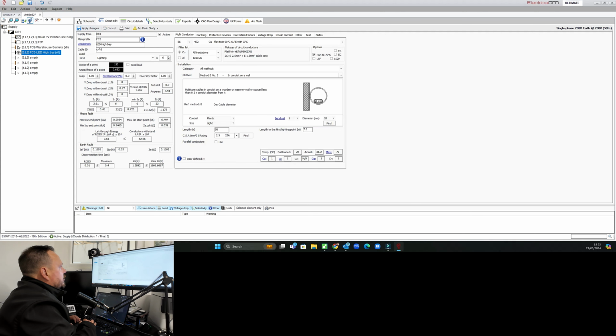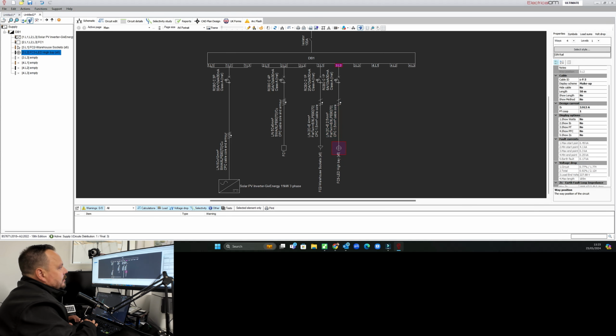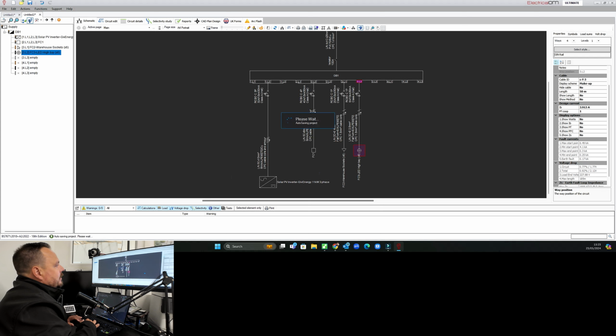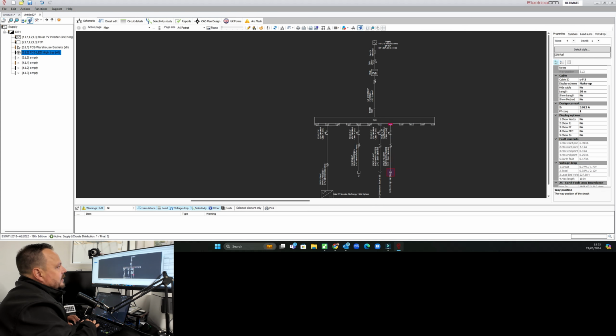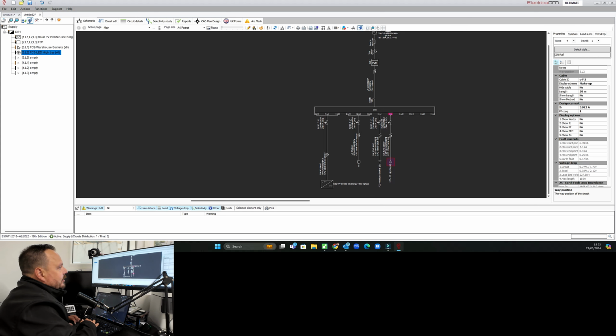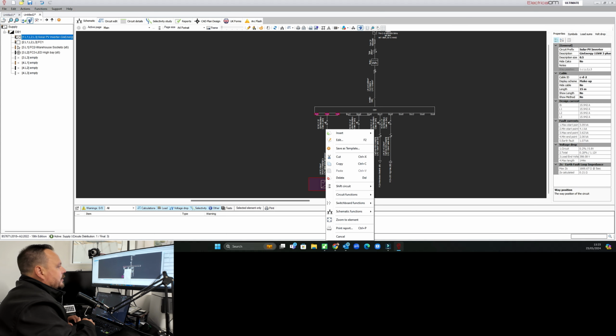So if we apply those changes, go back to the schematic, and we can have a little look here again. So we've got our RCBO in circuit, we've got our final circuit, and we've got our lights. So if I zoom out a little on that, you can kind of see the layout a bit better. But we've got our supply right at the top, running through that fuse into the meter. We've then got an isolator pre the distribution board. We've then got our PV. We've got our EV, and we've got these 2 final circuits for lighting and power. We are missing our strings.